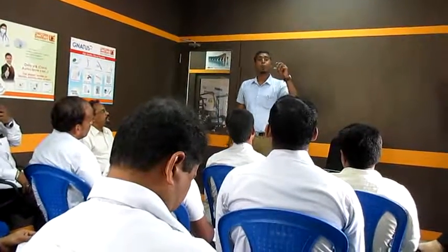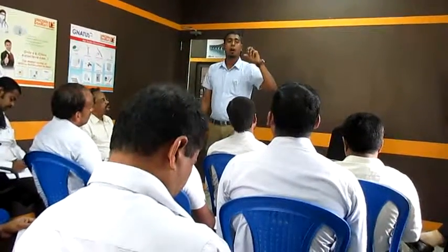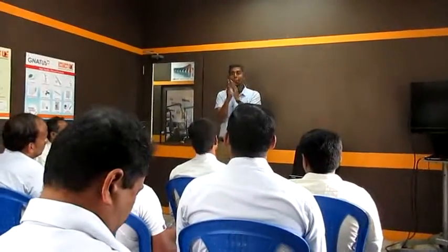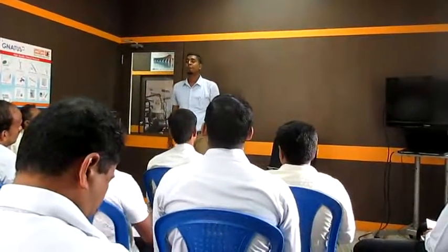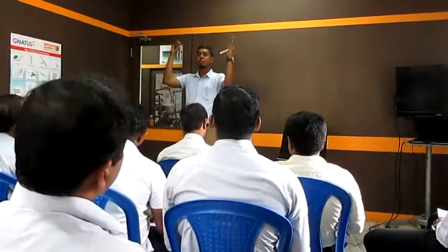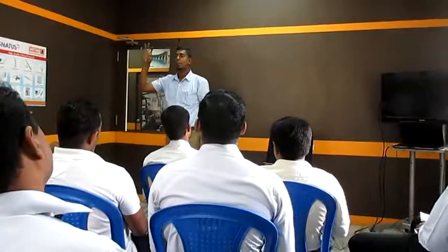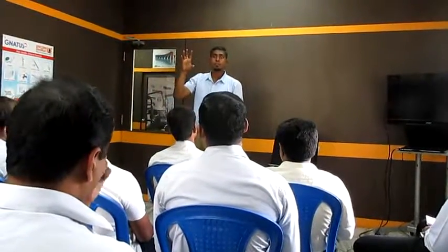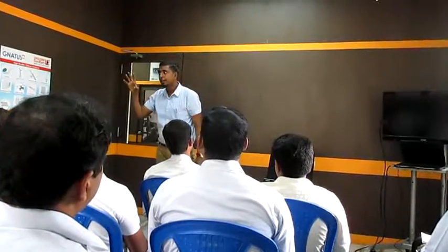Focal spot increases with time. How does the focal spot increase with time? The focal spot will never become smaller; it will always become bigger. Why? Because the electrons hit and heat it, and it expands. A bigger focal spot means more blurring, and lesser sharpness.